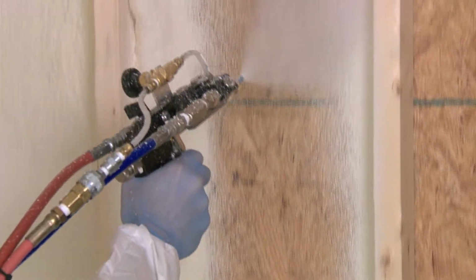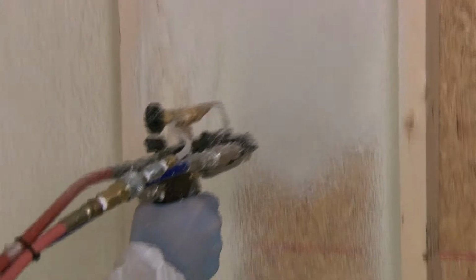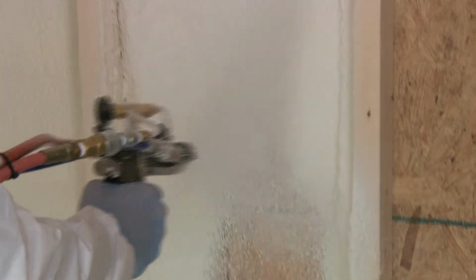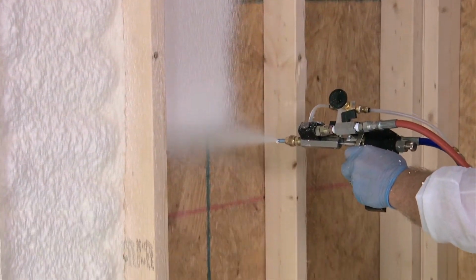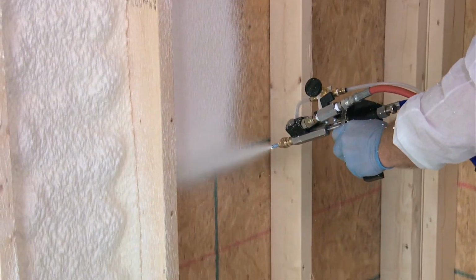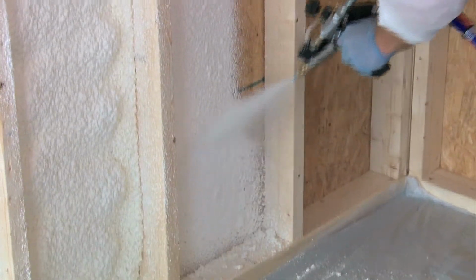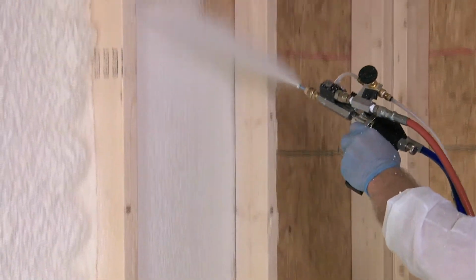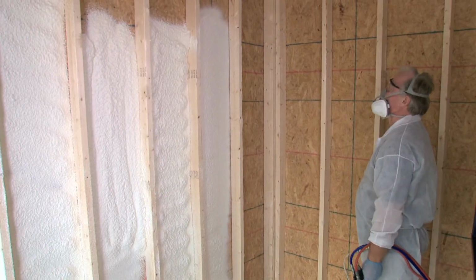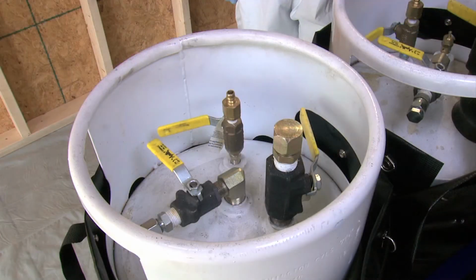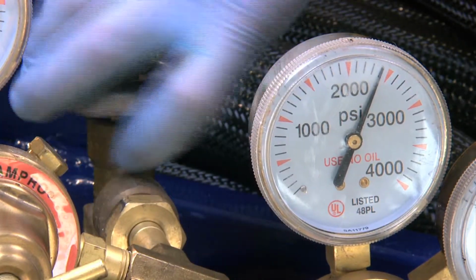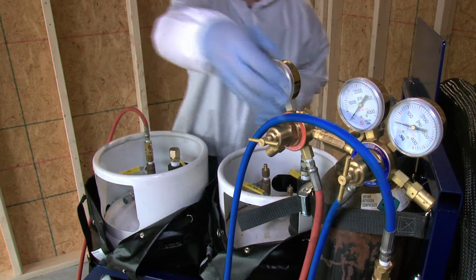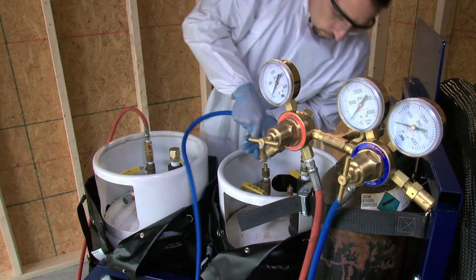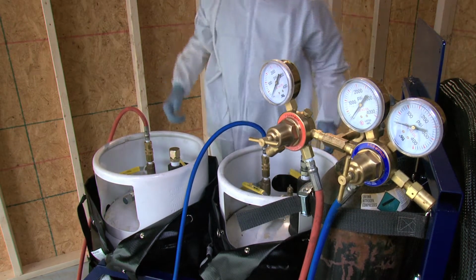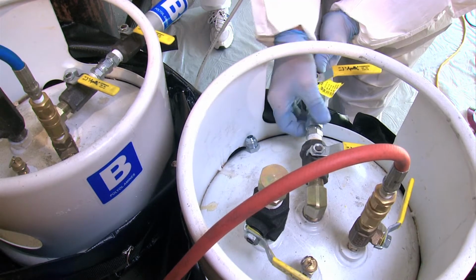Calibration should be checked at system startup, approximately halfway through a normal workday, and if the temperature changes by more than 10 degrees Fahrenheit. Calibration should also be checked if foam quality becomes noticeably different and whenever maintenance is performed on the system. Make sure that the dispenser, the chemical cylinders, the nitrogen cylinder, and all hoses are installed as described in the startup procedures. Check all hose connections to be sure that there are no leaks.